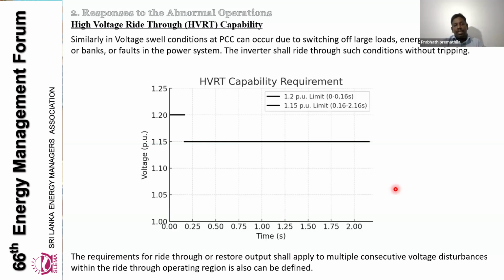But if we are able to have the inverter operate with the LVRT and HVRT facility, it will stay connected to the network and give support during a voltage disturbance. As I explained, there are inverter capabilities. In some situations we may have a few consecutive disturbances, but as per the inverter capabilities and the latest standard, it is defined how many disturbances they can support. That facility is available. They can ride through a few disturbances and manage our network during such a voltage disturbance.